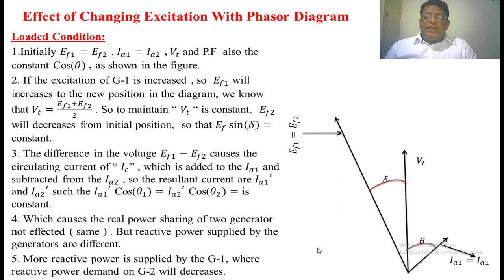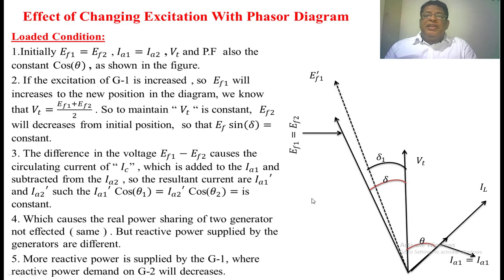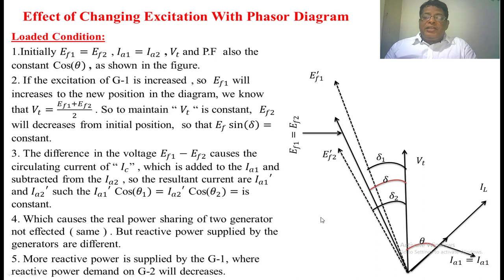Whenever we increase the excitation of the first generator, EF1 will increase. That new phasor is taken as EF1 dash, shown with a dotted line. We know that the terminal voltage equals EF1 plus EF2. When EF1 increases to EF1 dash, EF2 must change to maintain the terminal voltage as constant — shown as EF2 dash. So there is a difference between EF1 dash and EF2 dash, and this resultant voltage will be experienced in the loop of the two parallel alternators.